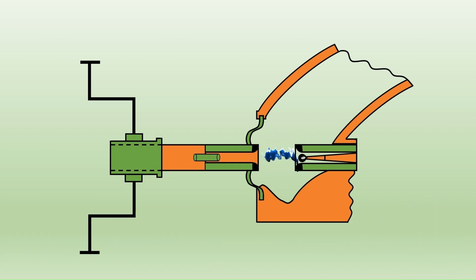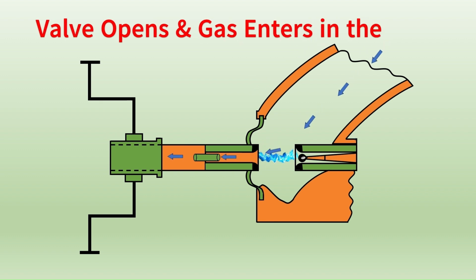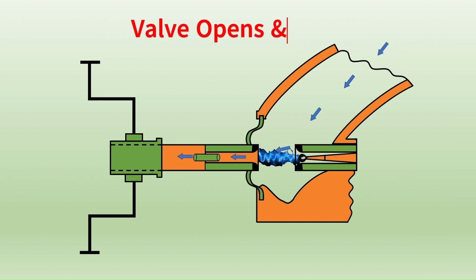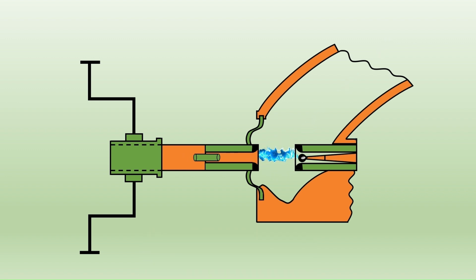The valve connected with the SF6 gas tank will open and the gas will enter the arcing chamber. Now SF6 gas will flow through the arc and it will quench the arc in a very short time. After the extinction of the arc and interruption of current, the gas moves out from the gas outlets and it will get reconditioned for further use.